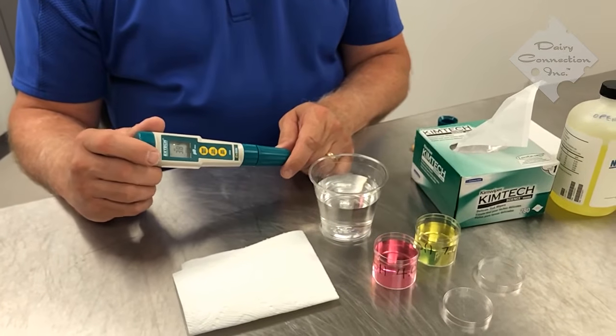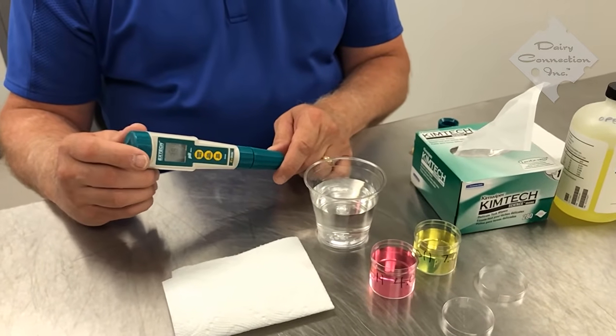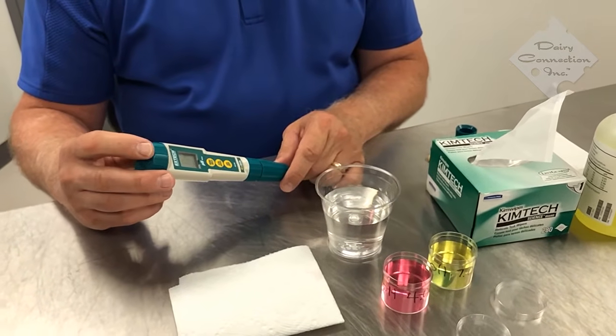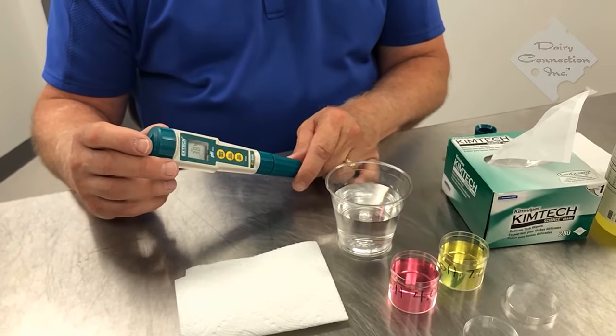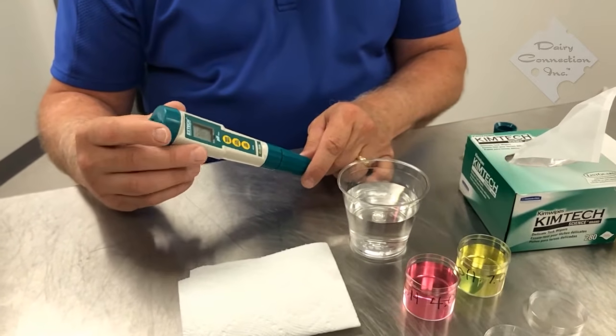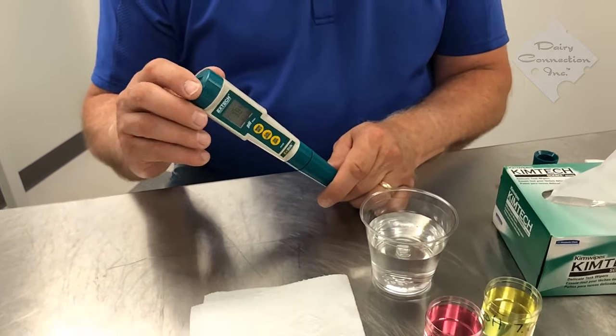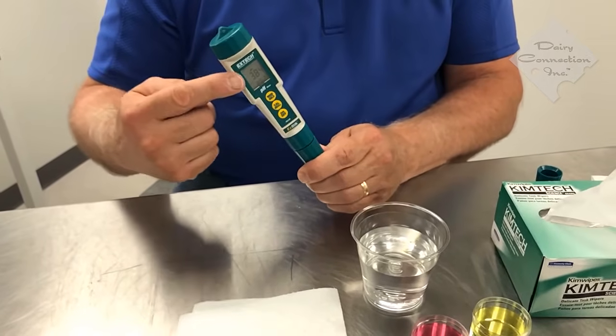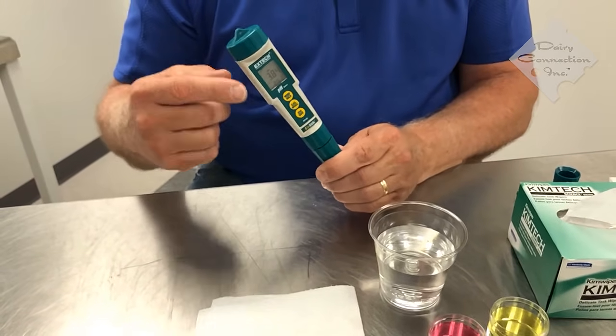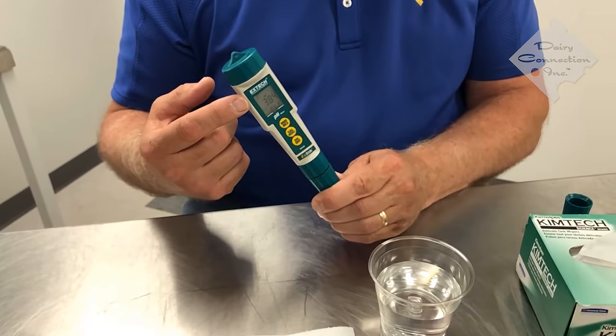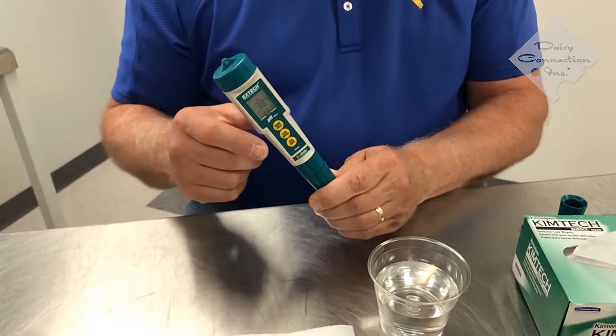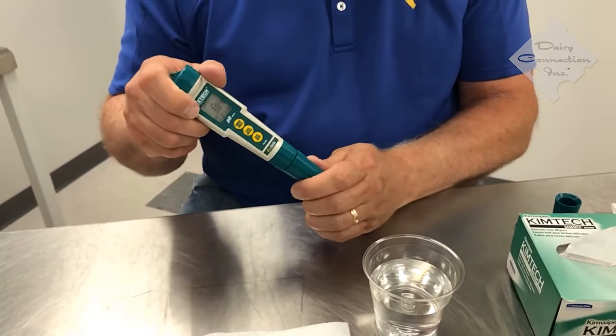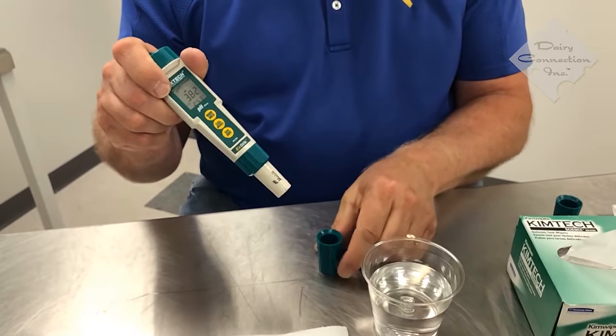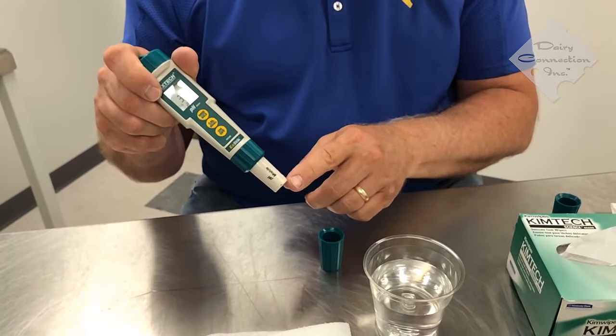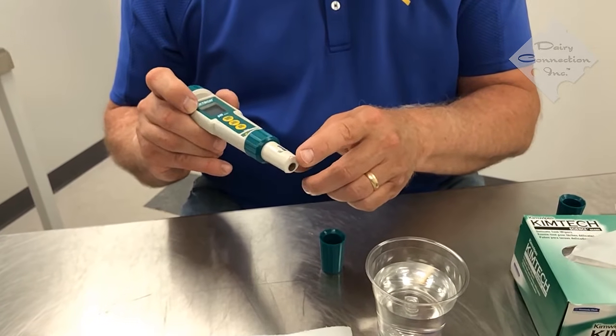So first I'd like to go through the parts of the Extech 100 pH meter. When you first pull it out of the box, it's important to know what each part or the description of the items are. So this is a digital display, and the part right here is called the body of the pH electrode. This is where you're going to have the actual reading of the pH. The second most critical point on here is going to be the actual electrode tip. And this is the part right here. The measurement takes place at the very bottom.